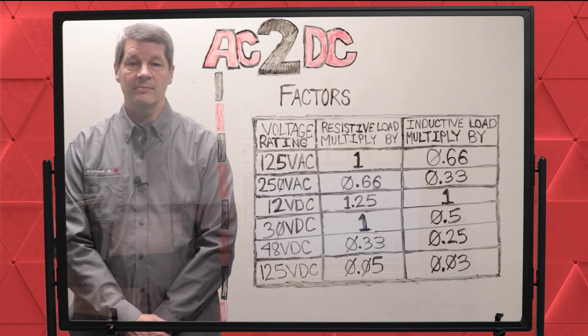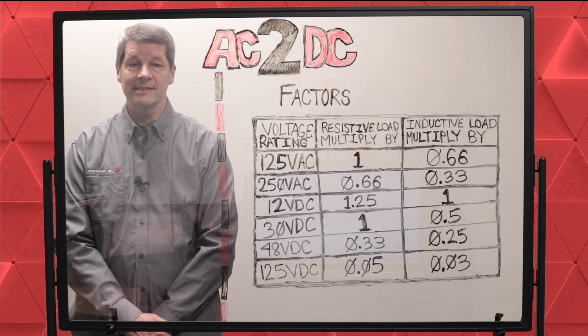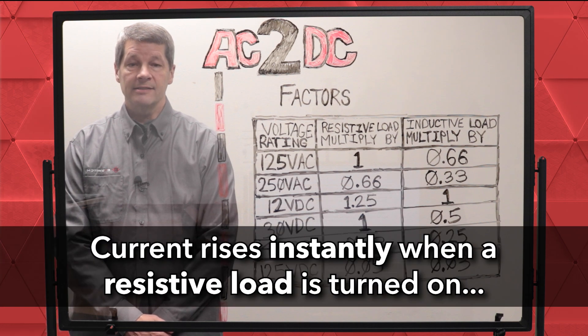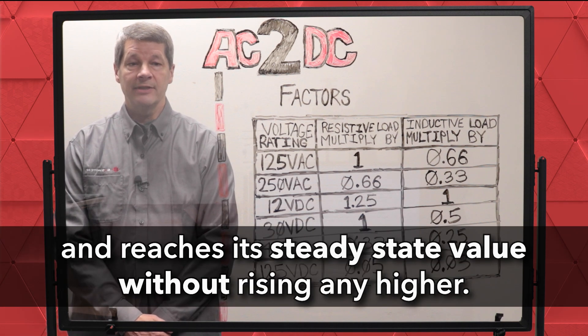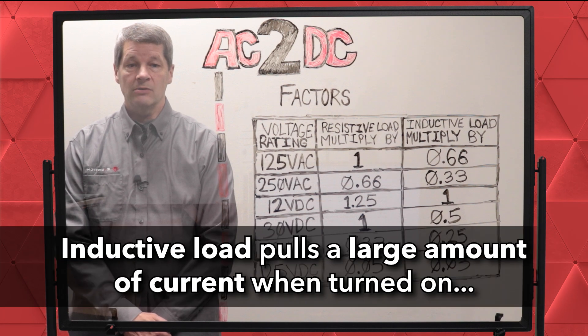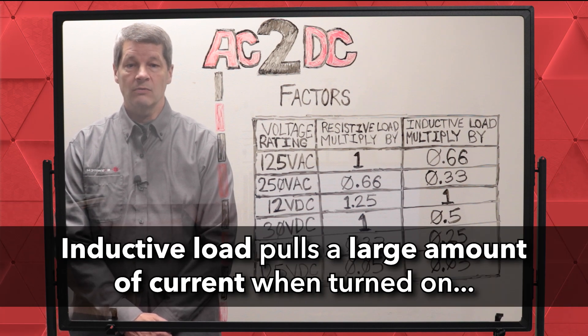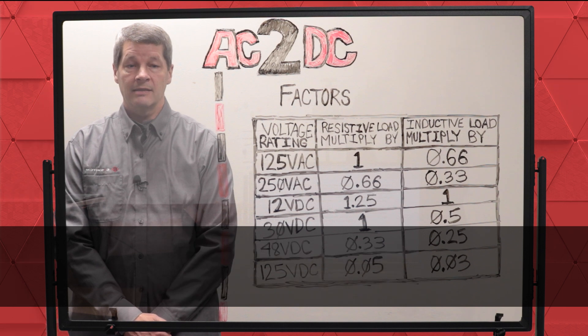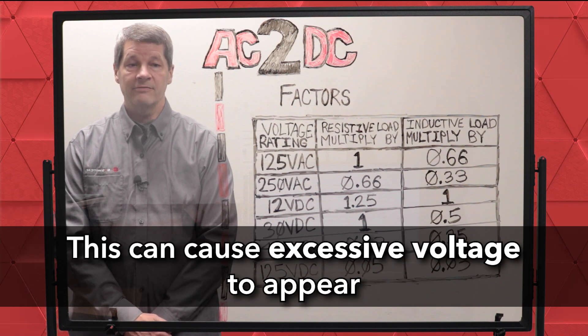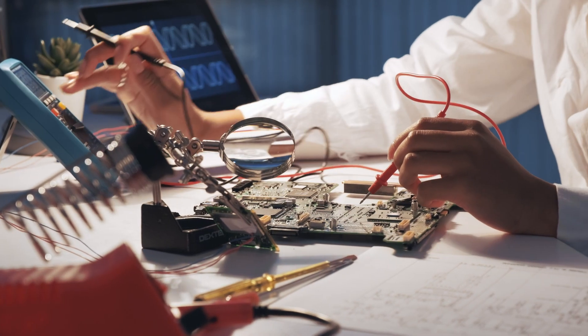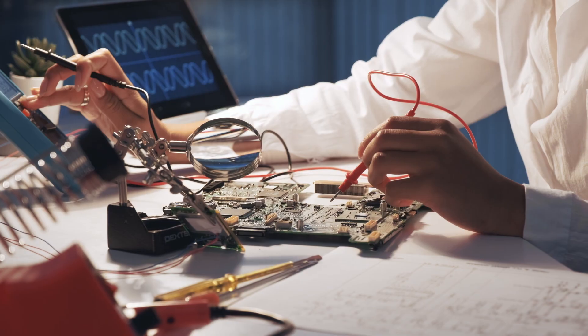Another key factor is determining if you're switching a resistive or inductive load. Current rises instantly when a resistive load is turned on and reaches its steady state value without rising any higher. An inductive load, on the other hand, pulls a large amount of current when turned on before reaching a steady state value. This can cause excessive voltage to appear, so you'll need to ensure that the switch's ratings meet or exceed the circuit's requirements.